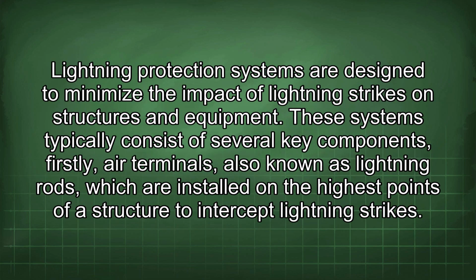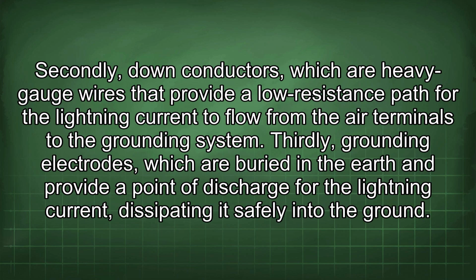Lightning protection systems are designed to minimize the impact of lightning strikes on structures and equipment. These systems typically consist of several key components. Firstly, air terminals, also known as lightning rods, which are installed on the highest points of a structure to intercept lightning strikes. Secondly, down conductors, which are heavy gauge wires that provide a low resistance path for the lightning current to flow from the air terminals to the grounding system. Thirdly, grounding electrodes, which are buried in the earth and provide a point of discharge for the lightning current, dissipating it safely into the ground.